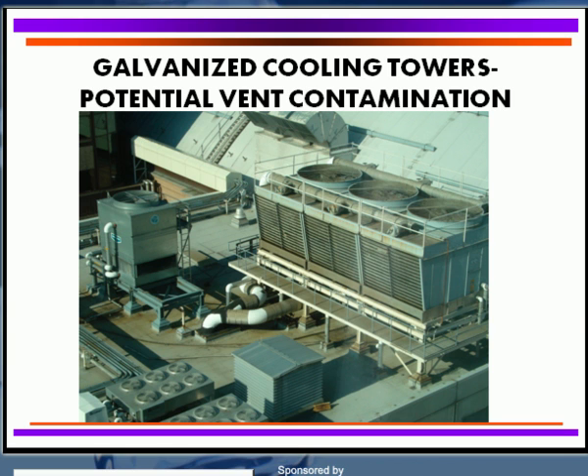Those vents may be spewing out various types of contaminants such as exhaust from toilets, food processing operations, cafeterias, and this type of thing. Those are areas that could cause serious problems, enhancing or causing a substantial amount of galvanized corrosion in those particular cooling towers. You also have to watch for bio buildup. Additionally, there are air coolers at the very bottom, and some of that warm air might be drawn right into the cooling towers, reducing the efficiency of the cooling system. The key question is: where is your cooling tower, what possible contaminants could be getting into it, and will it contribute to white rust or not?